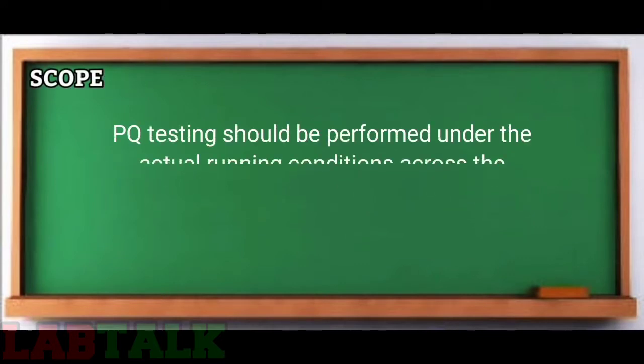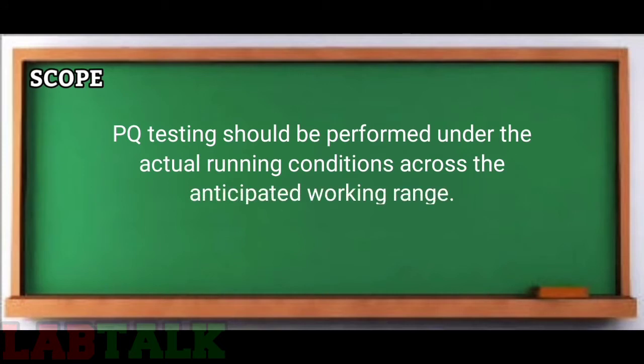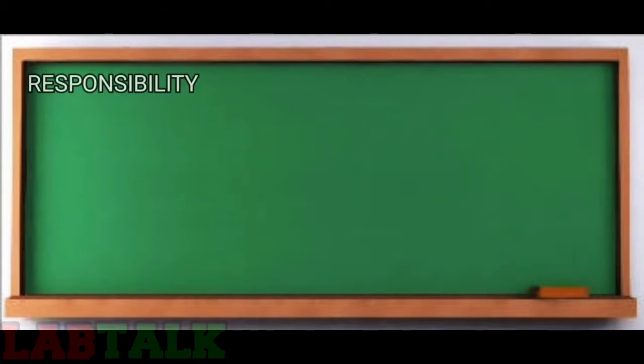Once IQ and OQ have been verified, PQ testing is conducted. Responsibility lies with the person who is going to operate the equipment or the technical specialist in the respective field.